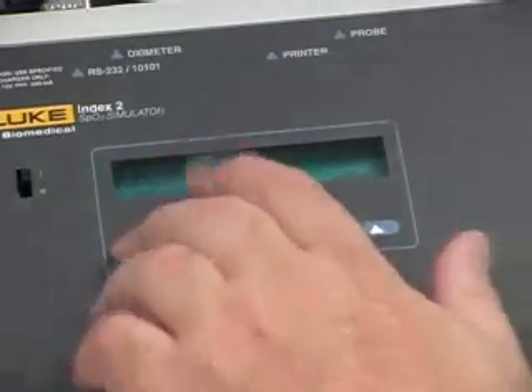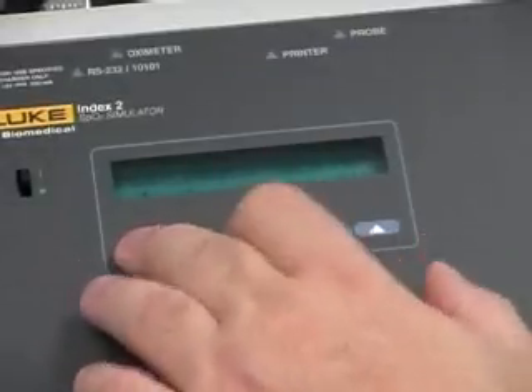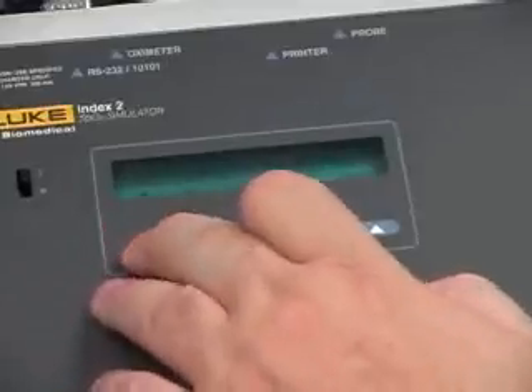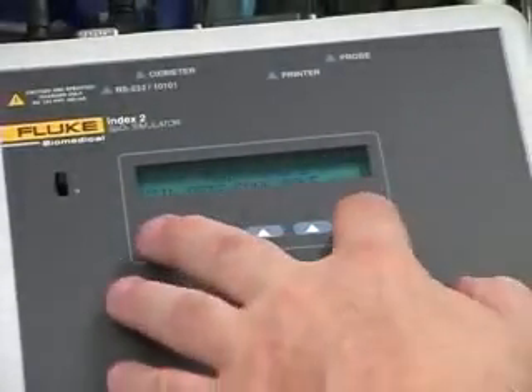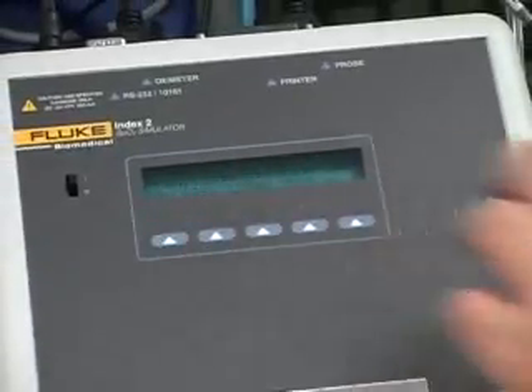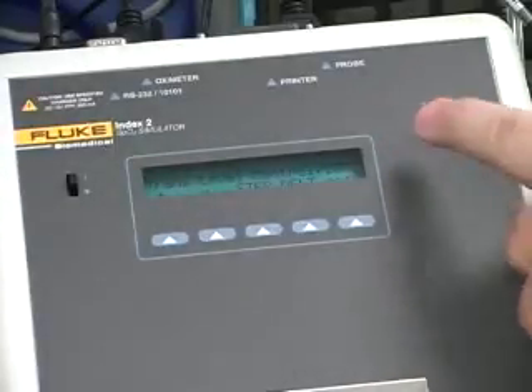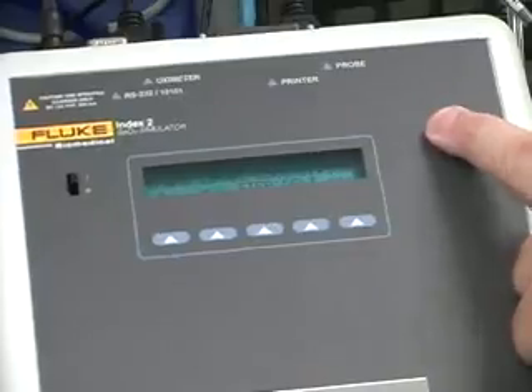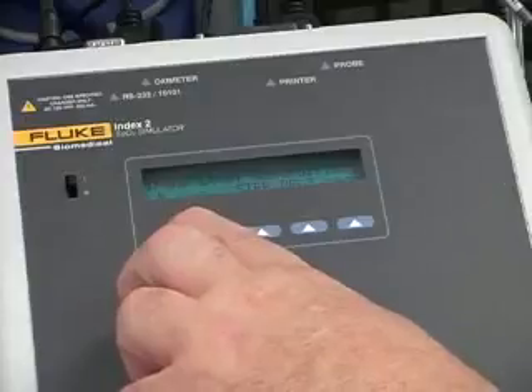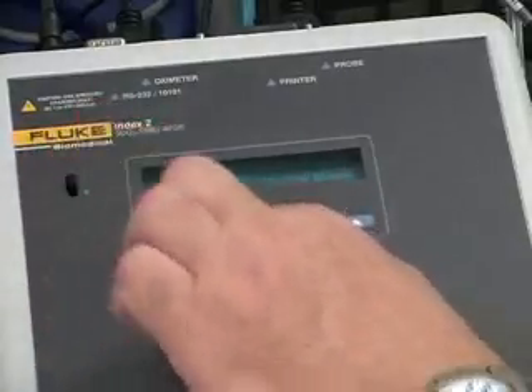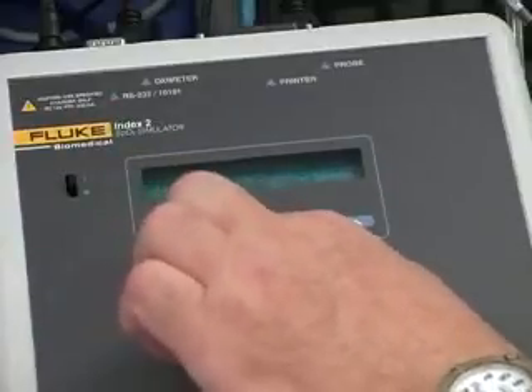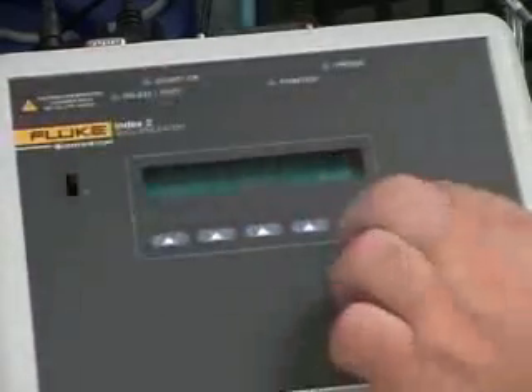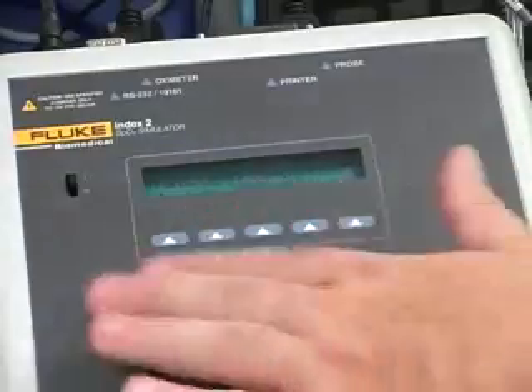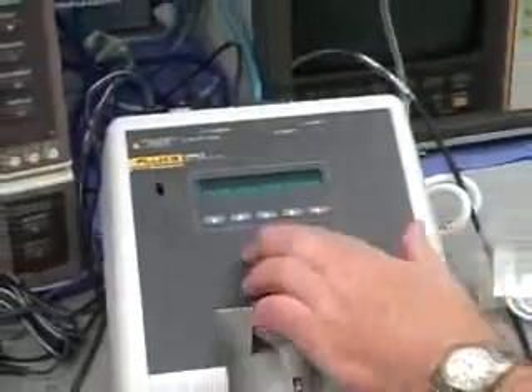So I can go in here. Yeah, it's preset here at 1,000. So if you're running Nonin Medical units, I would simply go into this menu and run it up to somewhere around 2,700 to 3,000. Unfortunately, you'll lose those values once you escape out of the simulation menu. As long as you're in the simulation menu, you'll be okay. But if you go beyond here, you will lose it.